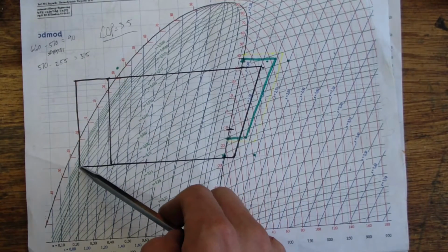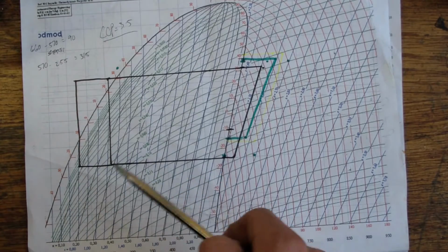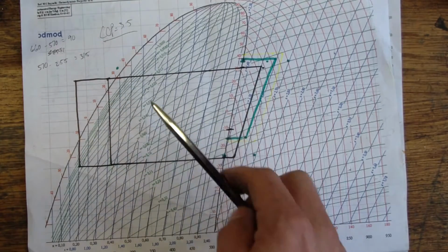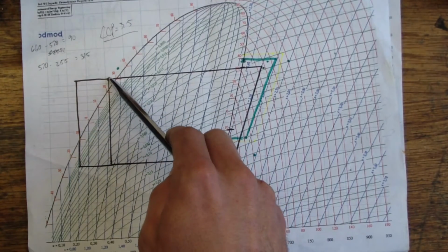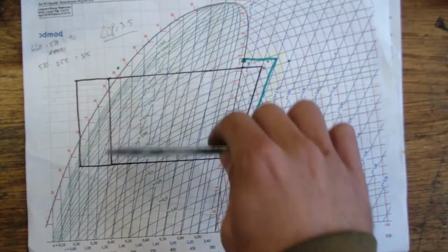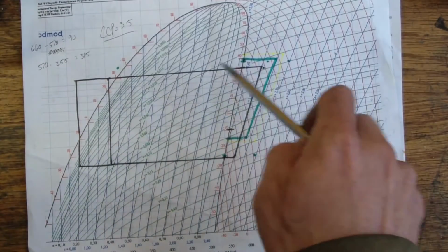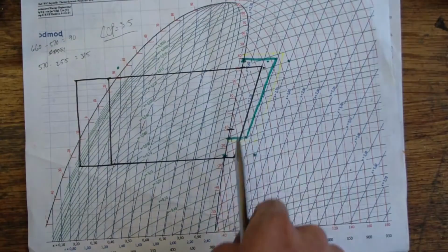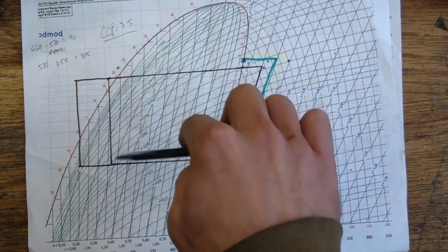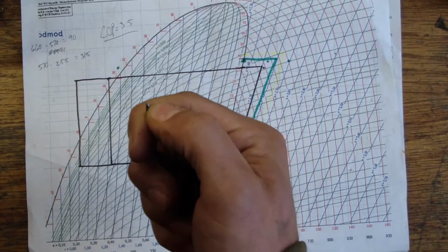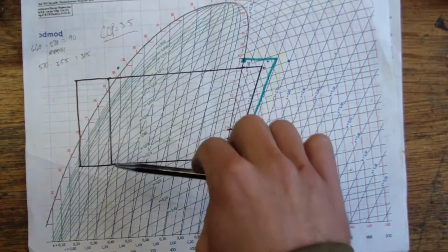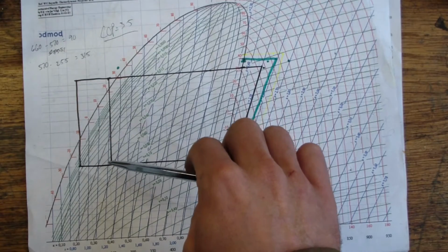Whenever we finally enter the throttling device and exit the throttling device, we have less flash gas. And flash gas is something that you can read about in any good refrigeration textbook. I'll try to discuss it a little bit here, but let's go with this line right here, and let's assume that we subcooled to that point there. We enter the throttling device. The difference in pressure here kind of dictates the flow through our throttling device. So that pressure component of the enthalpy up here, that is the pressure that was added by the compressor over here, and this pressure difference dictates the flow, and the pressure gets converted into velocity.